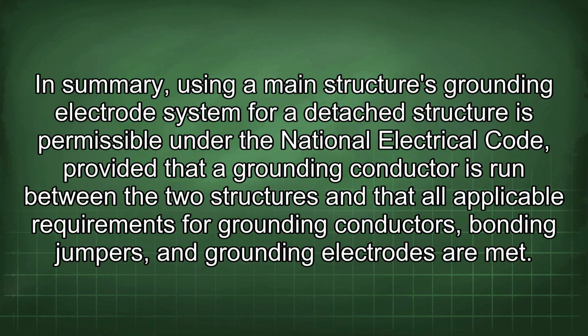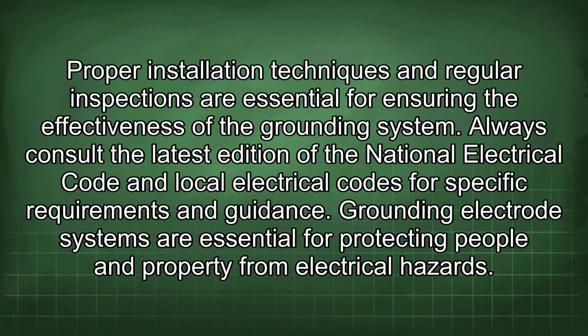In summary, using a main structure's grounding electrode system for a detached structure is permissible under the National Electrical Code, provided that a grounding conductor is run between the two structures and that all applicable requirements for grounding conductors, bonding jumpers, and grounding electrodes are met. Proper installation techniques and regular inspections are essential for ensuring the effectiveness of the grounding system. Always consult the latest edition of the National Electrical Code and local electrical codes for specific requirements and guidance.